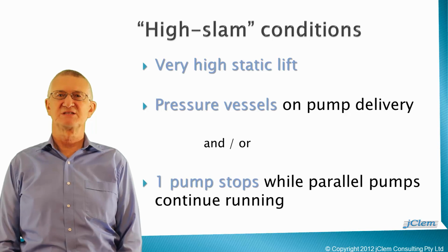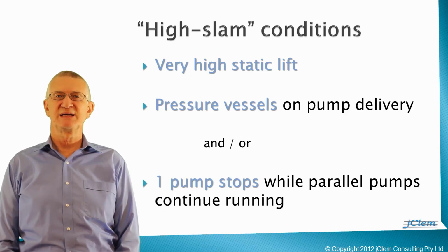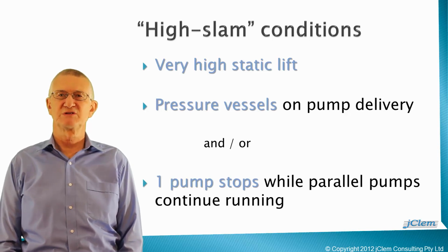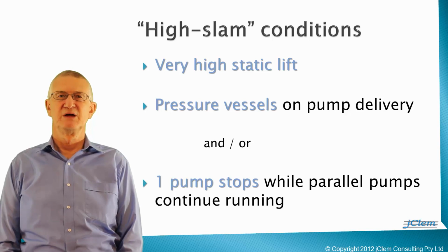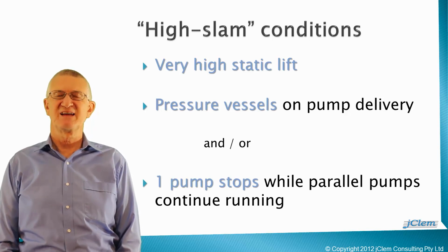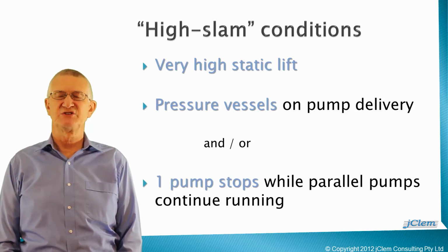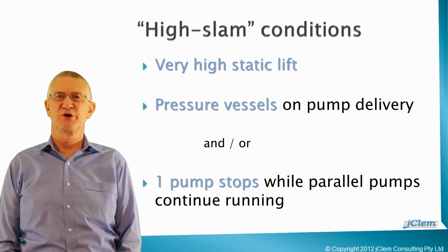1. In pumping systems with very high static lift. In these cases, the water column alone can eventually generate substantial reverse flow conditions. 2. When pressurized air vessels are installed on the delivery side of a pump station. These cases have stored energy immediately downstream of the non-return valves, which almost instantaneously reverse flow at the pump when a pump stops. And 3.